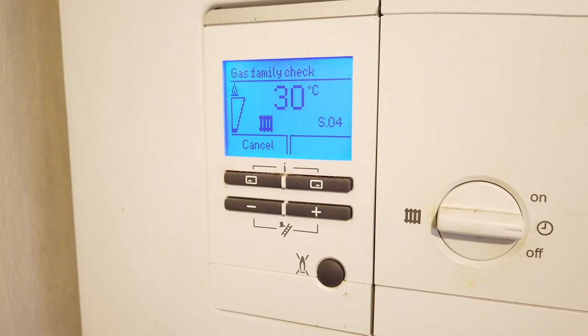As a word of caution, the settings are behind an engineer test mode. So unless you are a trained professional, you carry these out at your own risk and liability. Doing this test in a perfectly working boiler can under some circumstances cause it to stop working due to there not being sufficient air intake or other reasons. So it should not be carried out unless required.